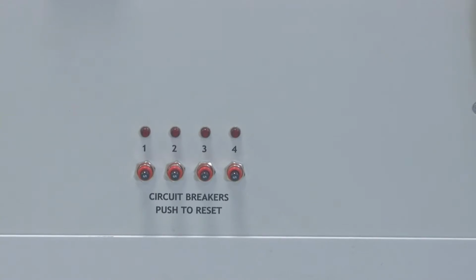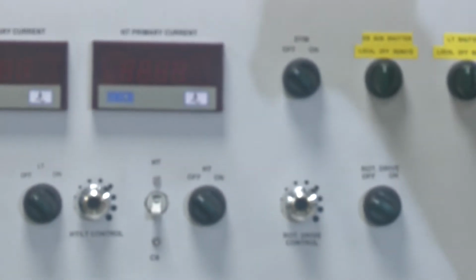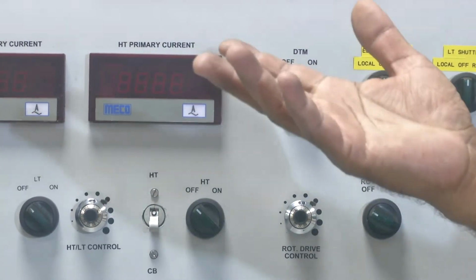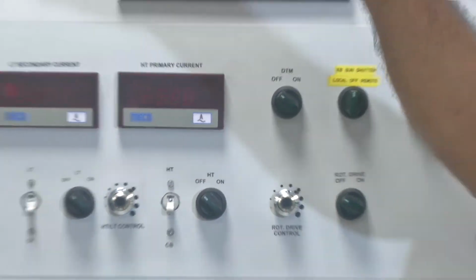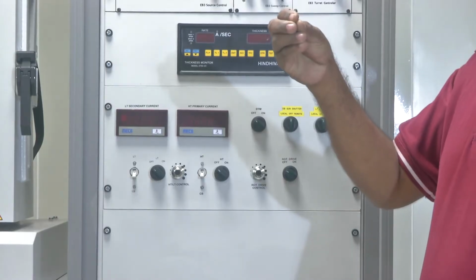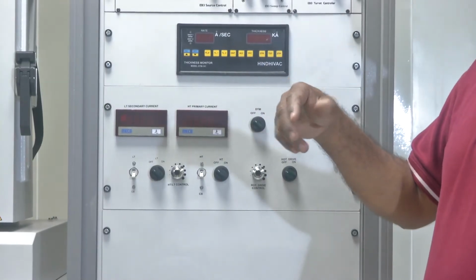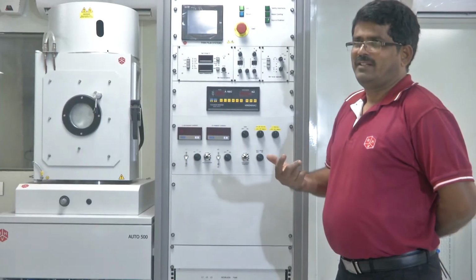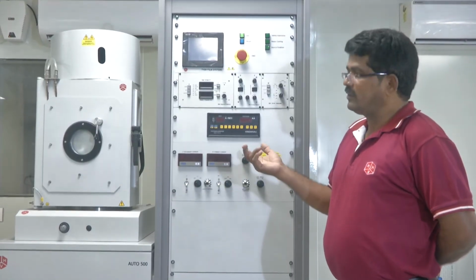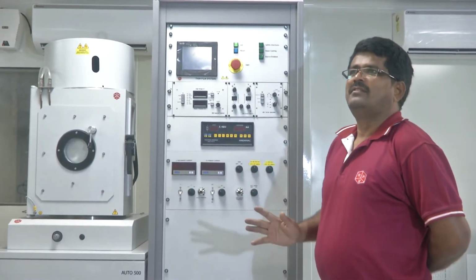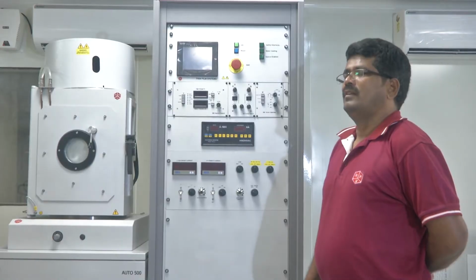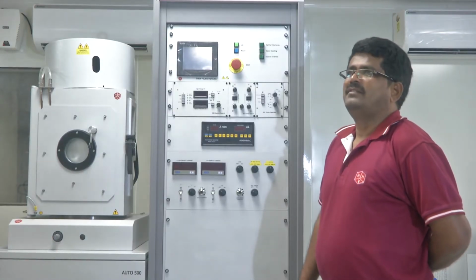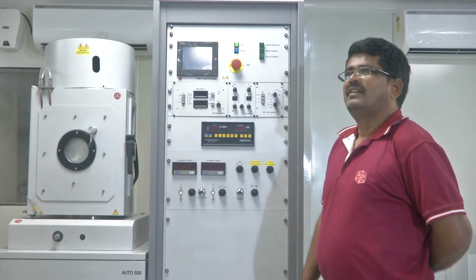After coating is over, just wait 10 minutes for cooling the substrate. Don't vent the chamber immediately. If the substrate is still hot and atmosphere goes inside, your sample will turn black and condensation will form. Otherwise, you can do venting with nitrogen gas. The substrate has to be cooled in vacuum condition, not in air.